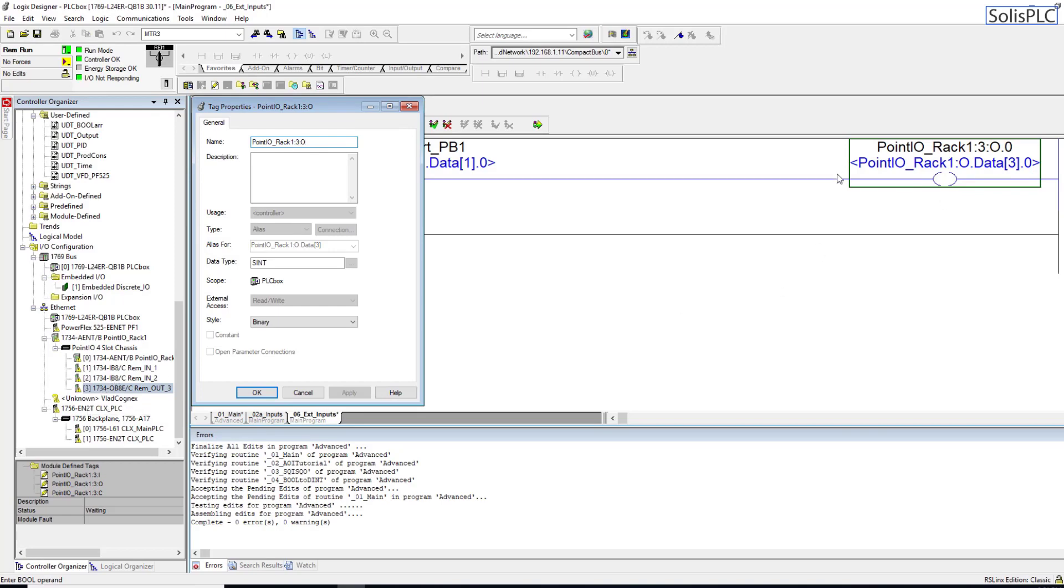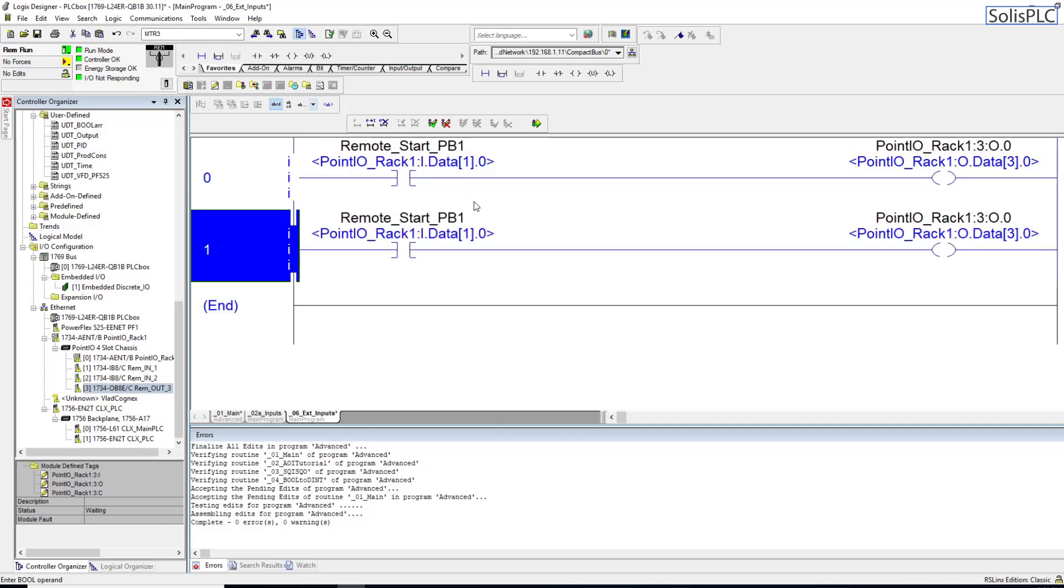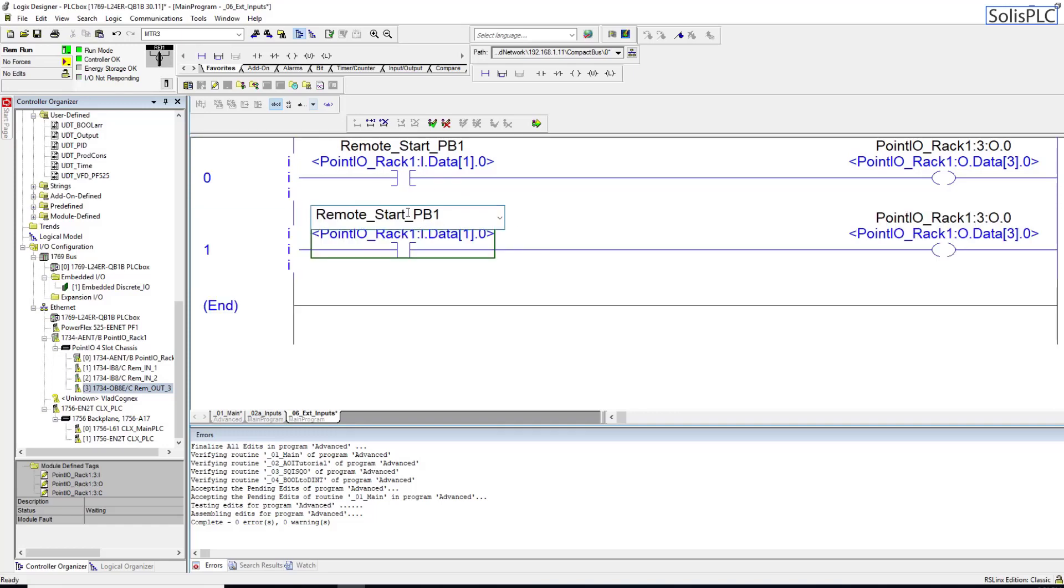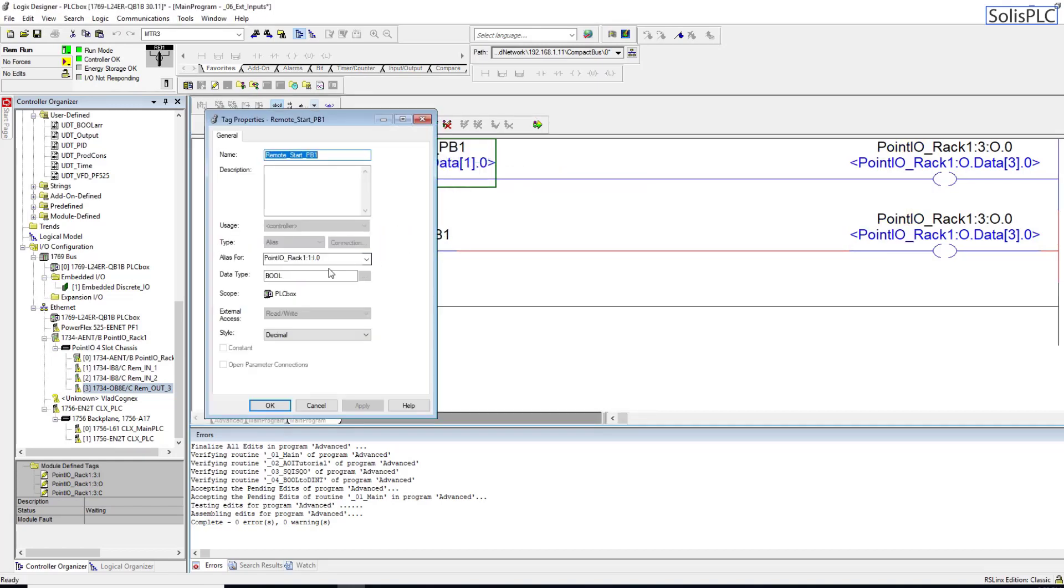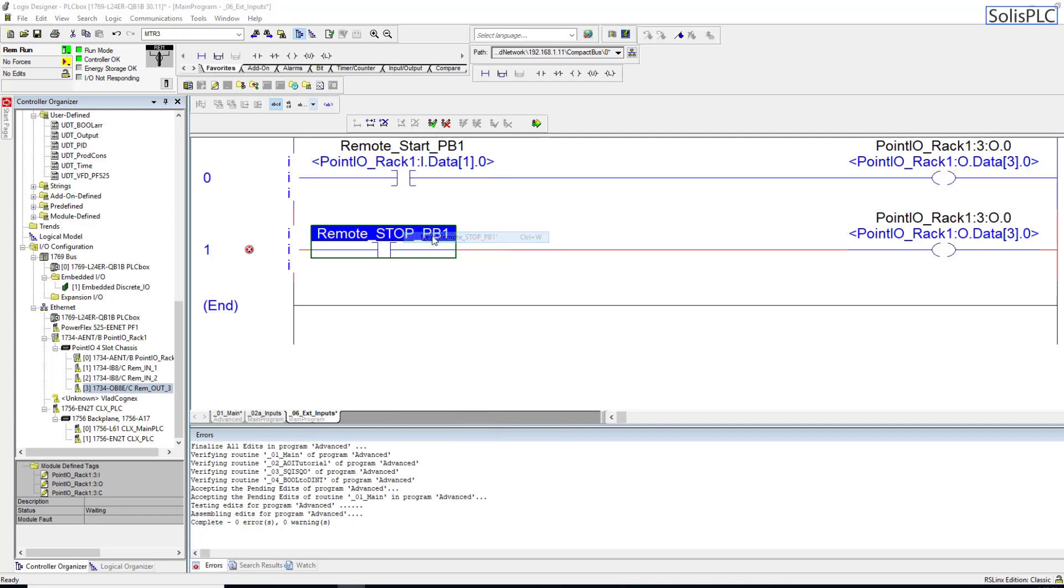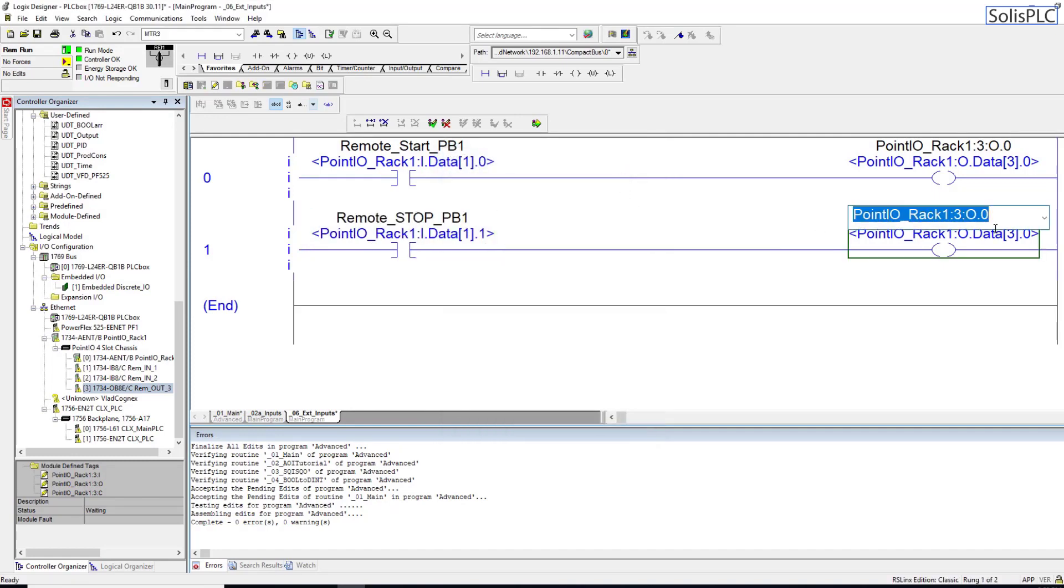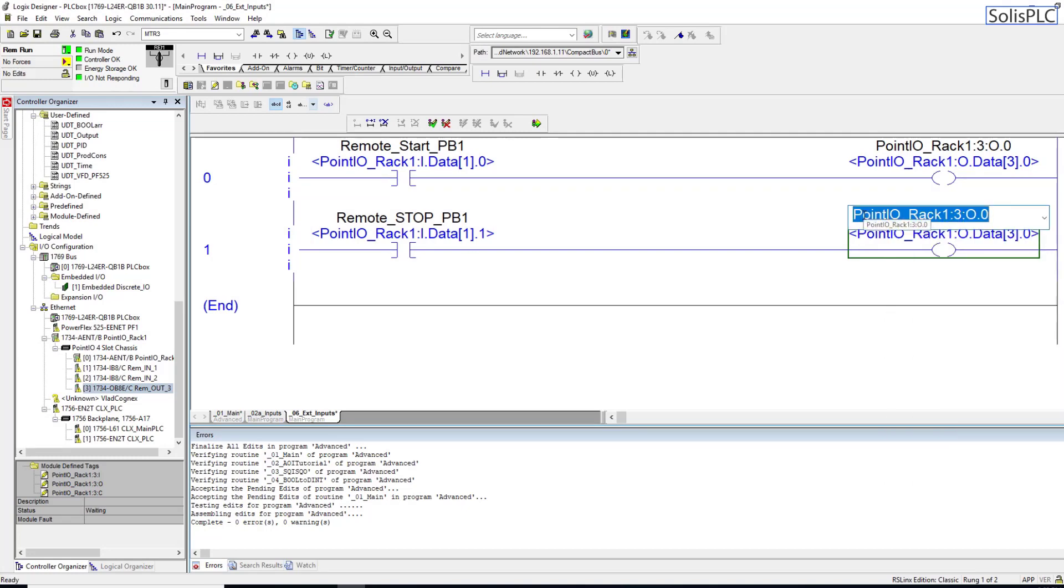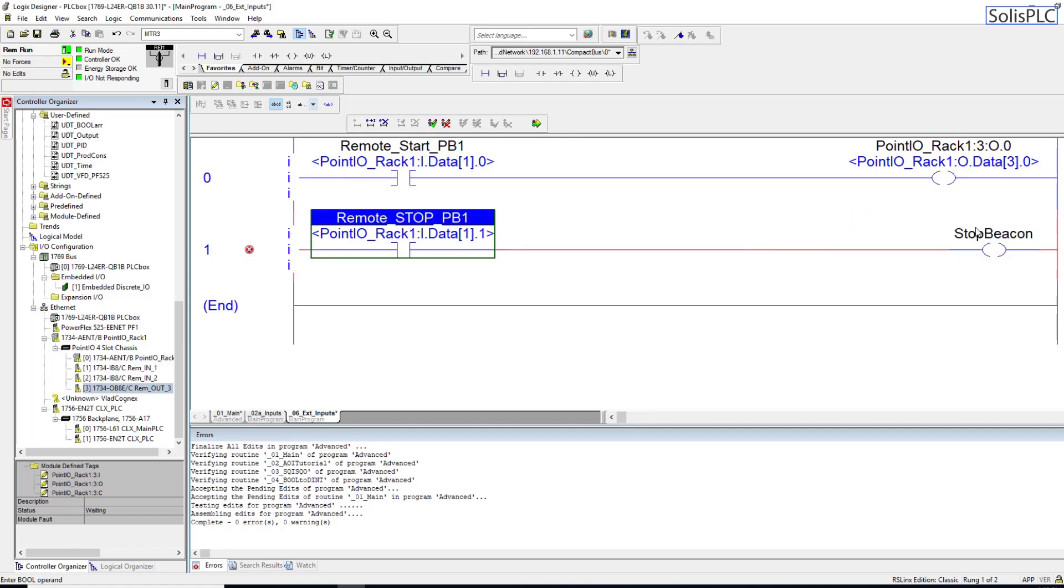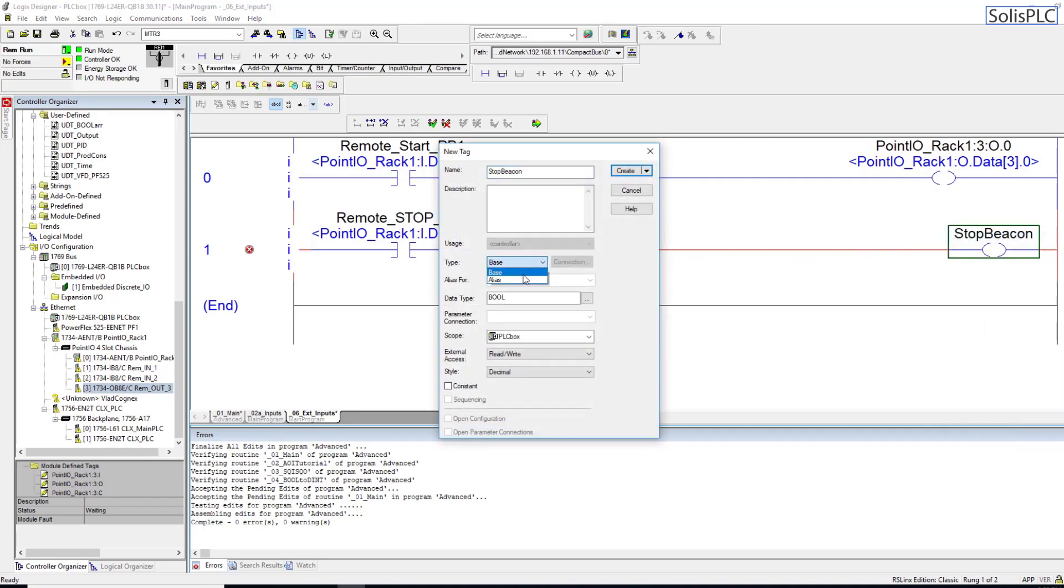Let's do another example - Remote_Stop_PB1. I'm going to go back into properties to copy this alias and increase it by one. I'm going to create a new stop push button. It needs to be selected as an alias tag, and for alias instead of this zero bit we're going to use bit one and hit create. For the output, just for sake of demonstration, this is going to be a stop beacon - if this is some kind of light which is going to be remotely positioned. I'm going to make that an alias and hit create.